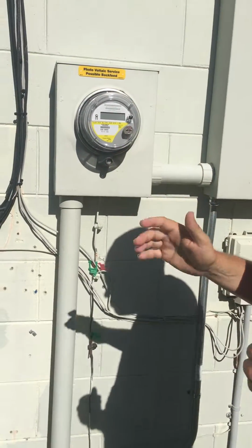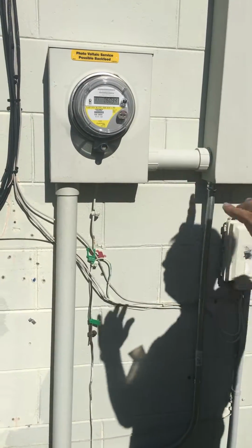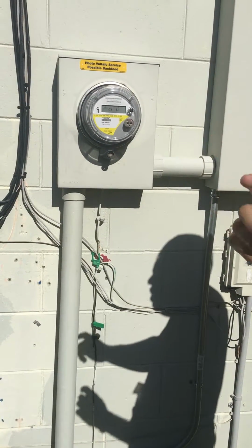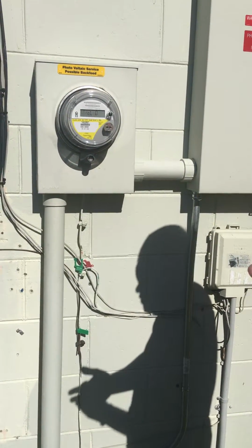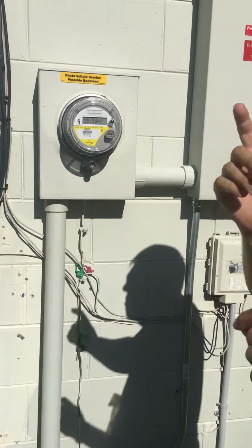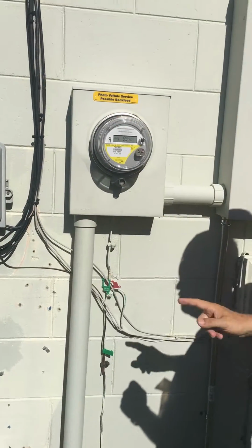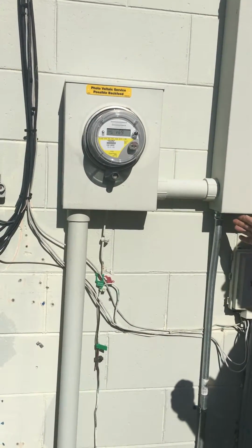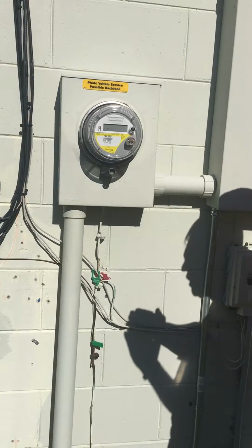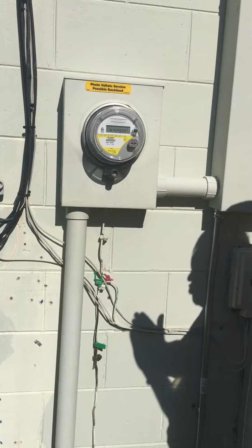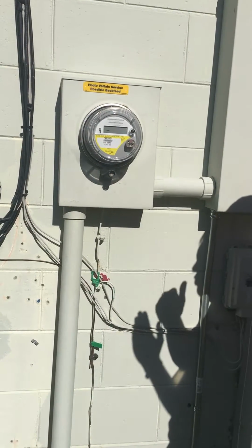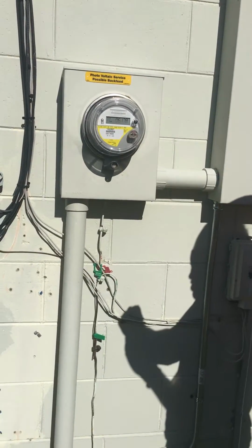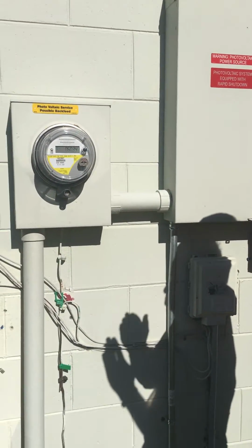But there's no switching between solar and utility, because the inverter is so smart. It's putting out utility grade voltage, phasing, and frequency. So it's monitoring the utility and mimicking the utility. In this panel where I have my utility connection and my solar connection, they're both exactly the same. What the solar inverter does to get the solar to be used first is increase the voltage by a very small fraction of a percentage of a volt higher, and voltage is pressure.